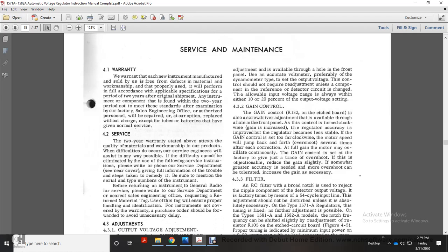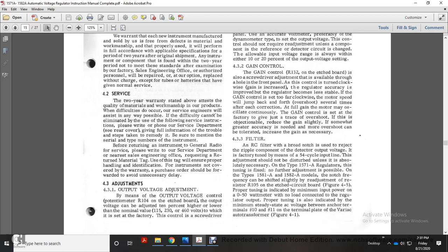4.3.2 Gain control. Gain control resistor 132 is on the etched board and is also a screwdriver adjustment available through the hole in the front panel. Turn the control clockwise to increase gain. The regulator accuracy improves, but the regulator becomes less stable. If the gain control is set too far clockwise, the motor speed will jump back and forth, overshooting several times after each correction. At full gain the motor also oscillates continuously. The control is set at the factory to give just a trace of overshoot. If this is objectionable, reduce the gain slightly. With a greater accuracy needed, more overshooting can be tolerated and increasing the gain is necessary.